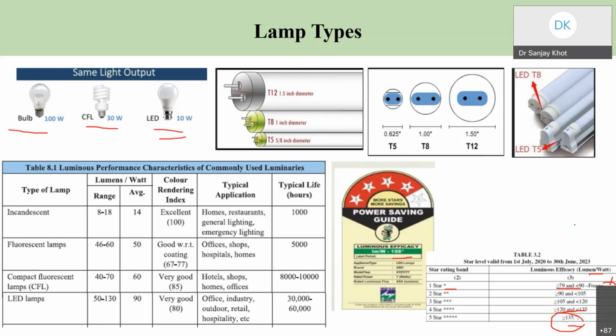Now suppose I want to shift that energy intensive tube light to an energy efficient tube light. Earlier I have considered it as 40 watt. In total there are 4 tube lights, so the total comes to be 160 watts. Now I'm using them daily for 6 hours, so annual working hours comes to be 2190. So the annual consumption for this working hour, considering this total wattage, comes to be 350 kilowatt hour, or electric units. Kilowatt hour means nothing but electric unit.